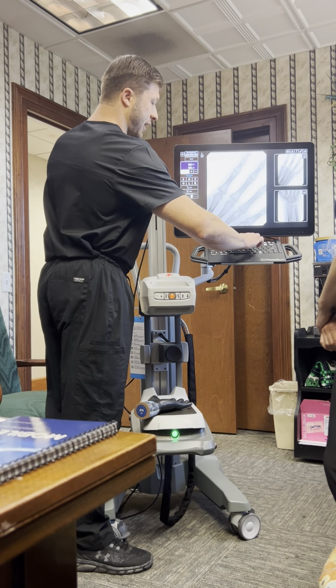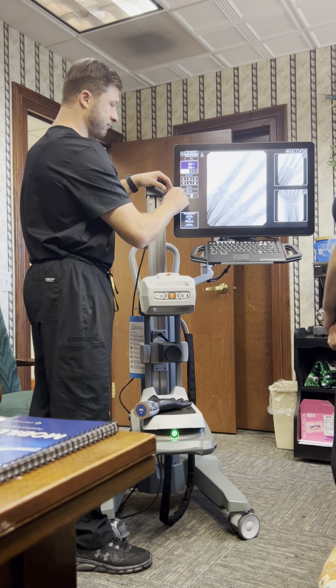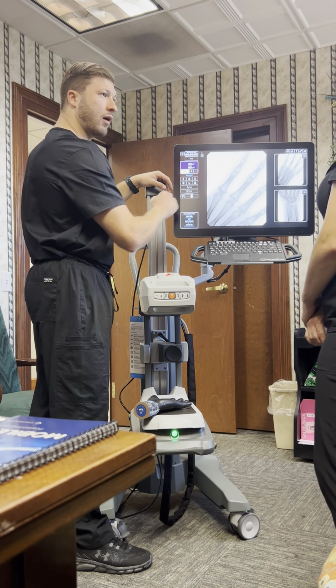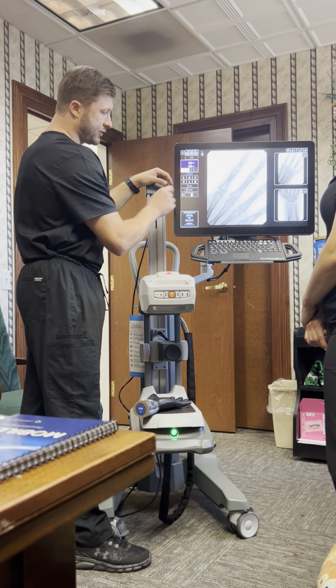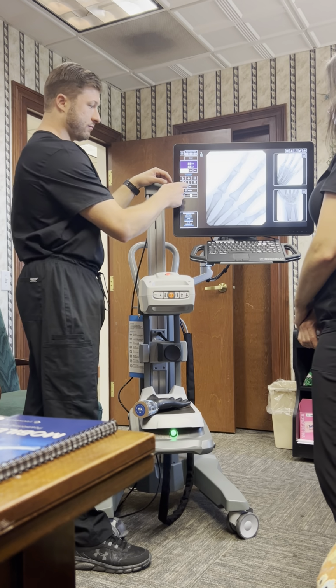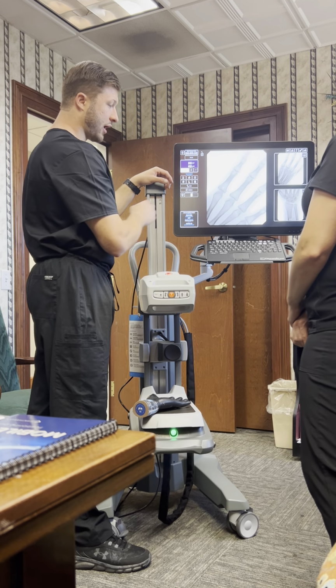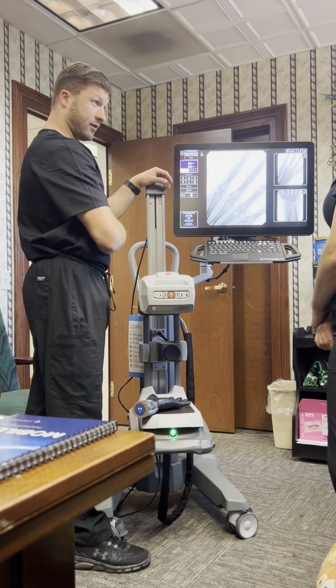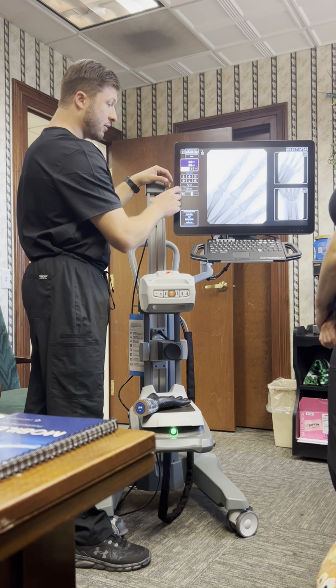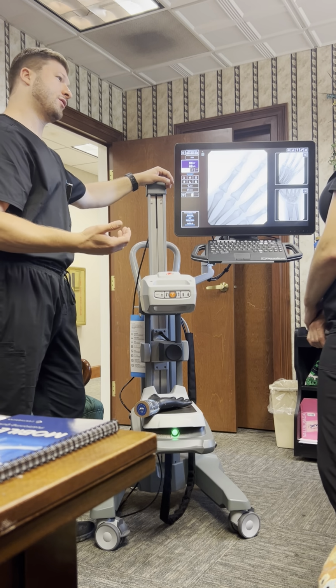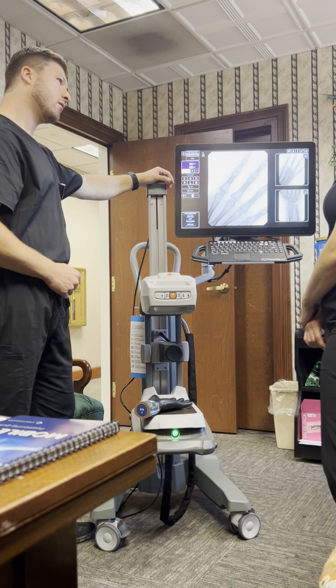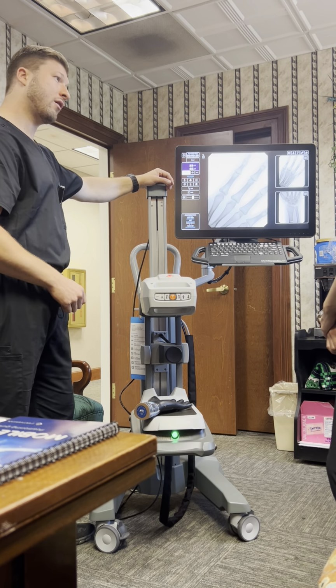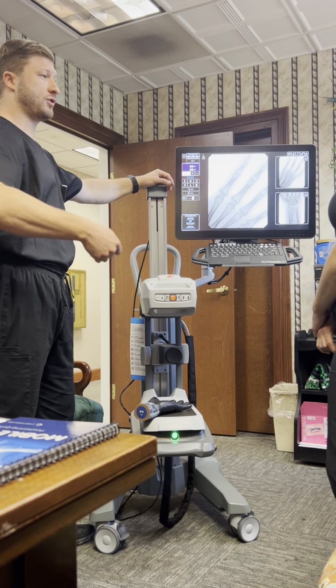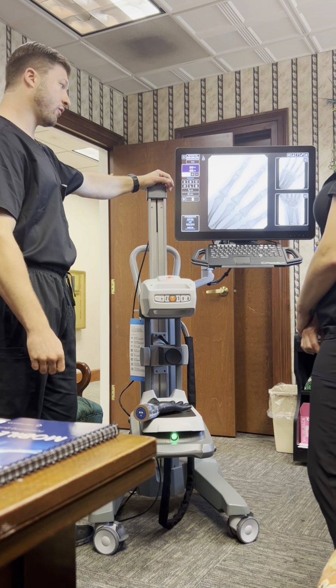Next we got still/motion, which is this auto icon right here. I wouldn't recommend touching it, because if you do, you're just telling the device I want to perform a fluoroscopic loop or still. I like to take a static image, but in auto, it'll recognize between the two after that third or fourth second of holding the foot pedal down, it'll just start doing 30 frames per second, continuous fluoroscopy for you.